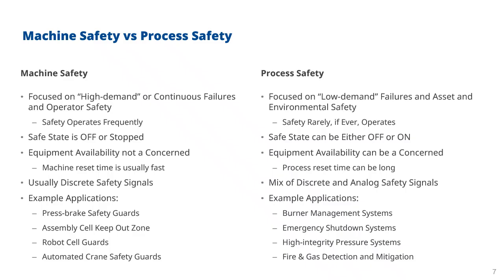Process reset time can be very long. If you shut a process down, it can be several hours or even days in order to restart the process back to where it was running and getting into its normal operating state. So avoiding spurious trips is important, but that's outside the scope of the safety system. That's an availability concern. Now, with process safety, we often find a mix of discrete and analog safety signals. And example applications include things like burner management systems, emergency shutdown or ESD, high integrity pressure systems, and fire and gas detection and mitigation or F&G type systems.